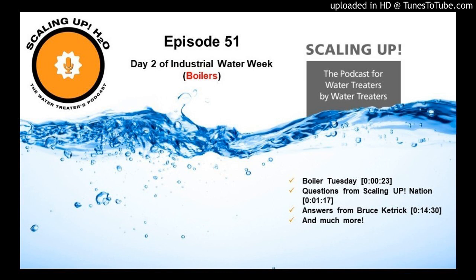The most dramatic change is that the blowdown of the boiler is based on silica levels. At that point, you're usually using demineralized water or what they call a desilicizer. A desilicizer is nothing more than an anion exchange tank from a demineralizer. And you monitor silica because silica is the first thing to be released from that anion exchange tank. Silica becomes critical because once it volatilizes, it will condense back out and become siliceous deposits on turbine blades or in other parts of the application.